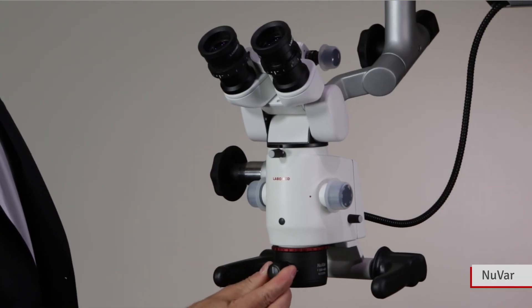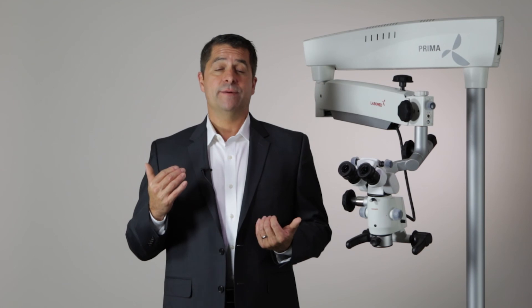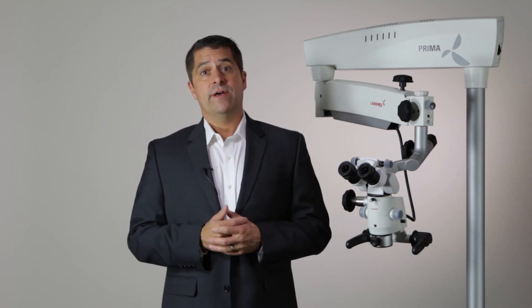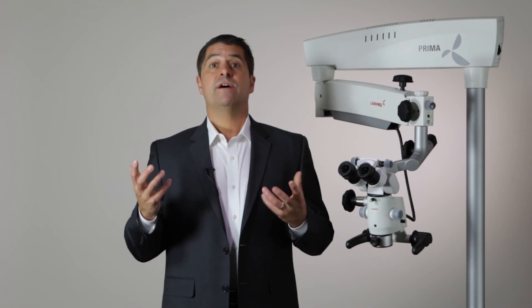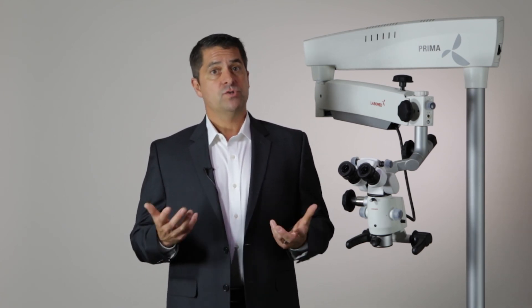The NuVar is a variable working distance objective with a focal length of 300 to 400 millimeters. Working distance is the distance between the microscope and the subject. Having a variable focal length means less repositioning of the microscope when focusing on different regions of interest or when a patient moves. A variable objective is also useful in multi-user environments with different working distance preferences. It's for these reasons that the NuVar helps new microscope users get over the learning curve quickly.